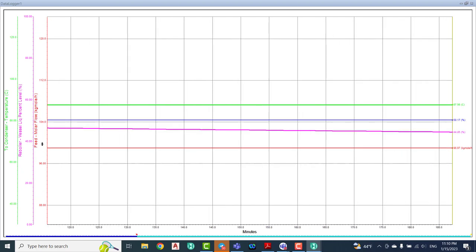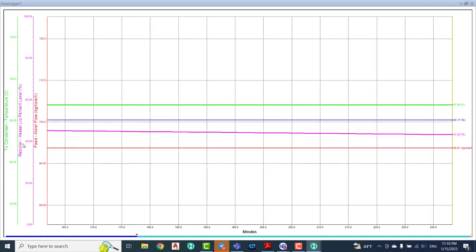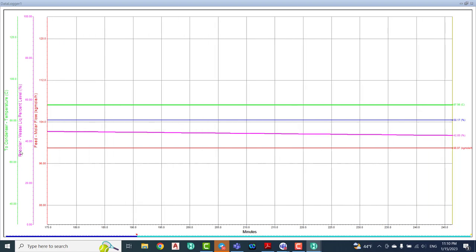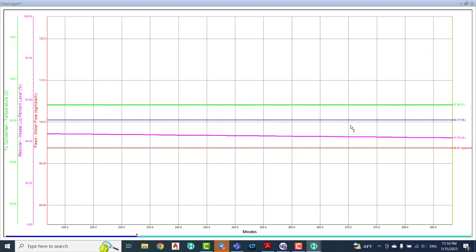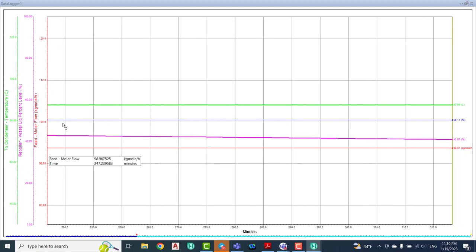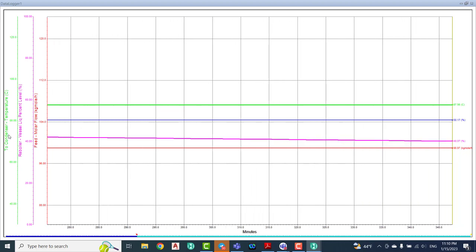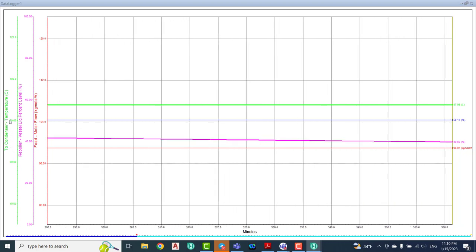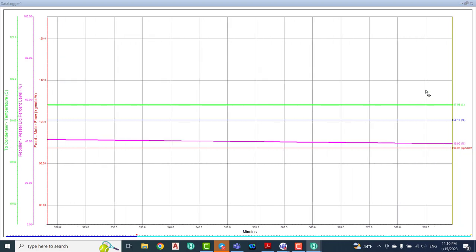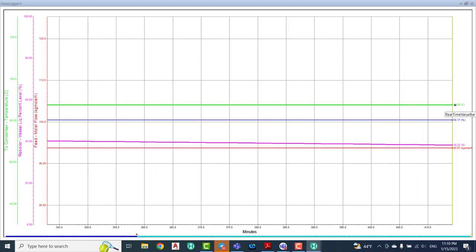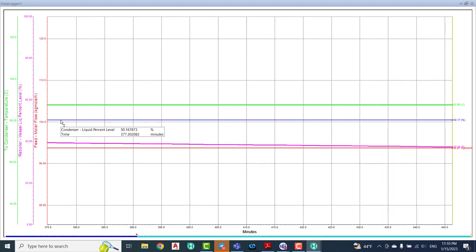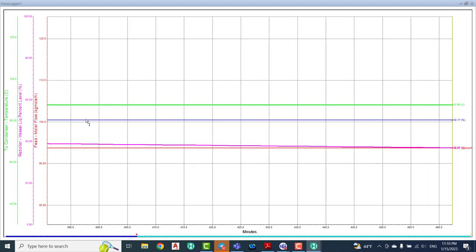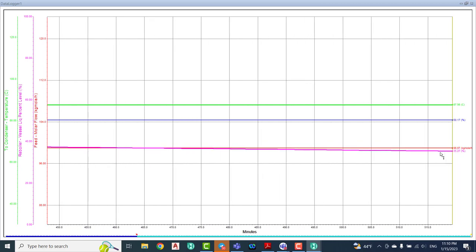Look in here, the feed we have in red, the purple we have the reboiler level, the blue we have the condenser level. The last one, the green, we have the condenser temperature. If we see the condenser temperature, we have 87. And below we have the condenser at 50, that means it's perfect. Just the reboiler level needs to increase.